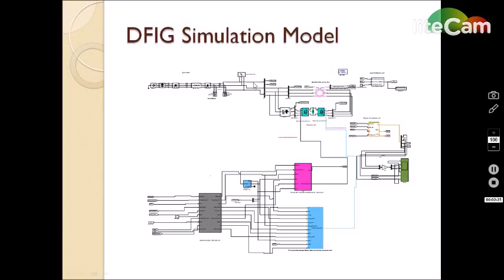This is the performance of the Doubly Fed Induction Generator without STATCOM. At 0.3 to 0.5 the current is distorted and voltage is distorted, because the DFIG can also generate reactive power when the fault occurs. As per the QV relationship the voltage is compensated, but the distortion in current is still there. This is the active and reactive power - when the fault occurs it generates reactive power.